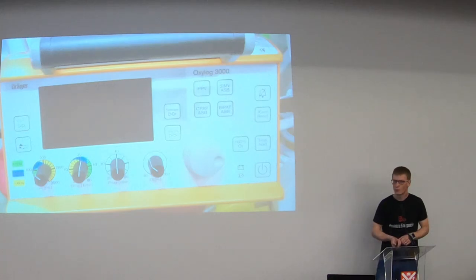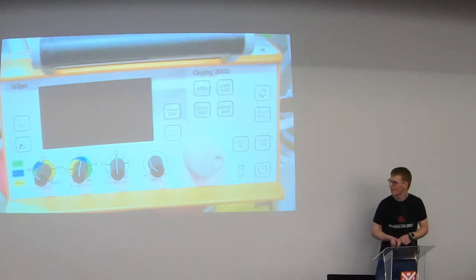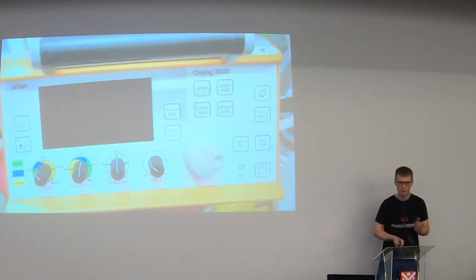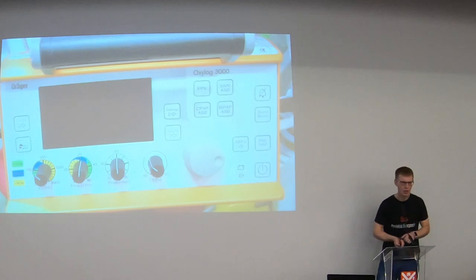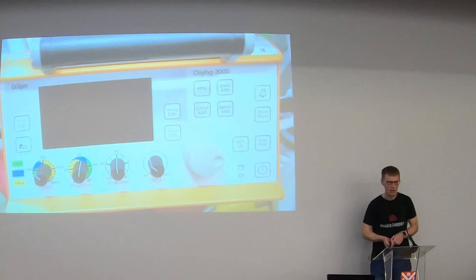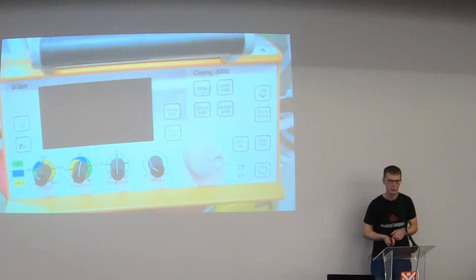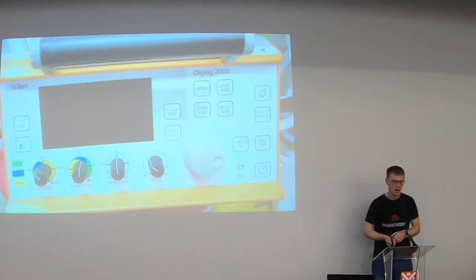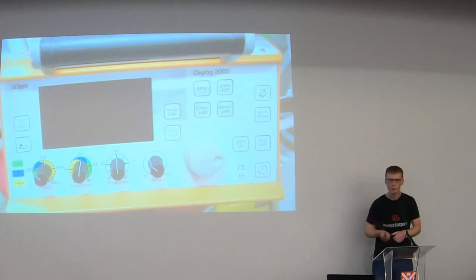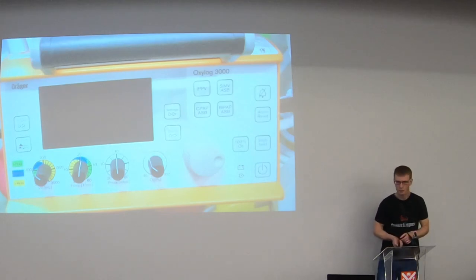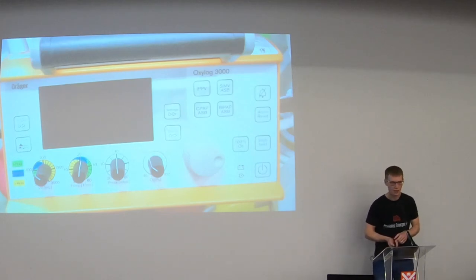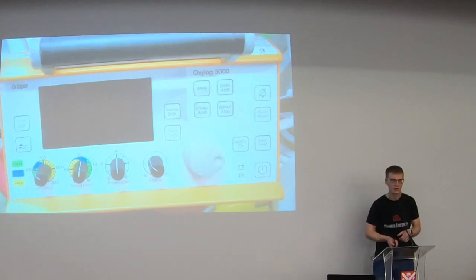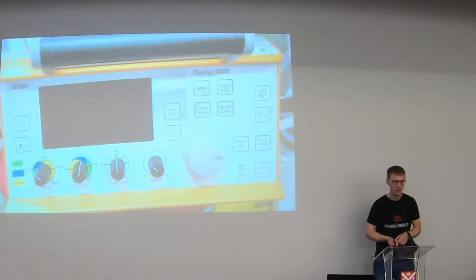Not such a fan of this one. I find it's less effective, much more dead space. Manufacturers say with this one it's okay from tidal volumes of 50 mils onwards. Although most transport guidelines are saying from 10 kilos onwards. I know if I'm trying to ventilate a 10 kilo child in this ventilator I'm probably dialling up 100 mils, 10 mils per kilo. But I'm ventilating the child plus a lot of dead space. The other thing with this one, be careful because there's two different circuits. There's a paediatric circuit and an adult circuit. The adult circuit has double the dead space of the paediatric circuit. So if you put a small patient on an adult circuit they're probably not going to ventilate particularly well.